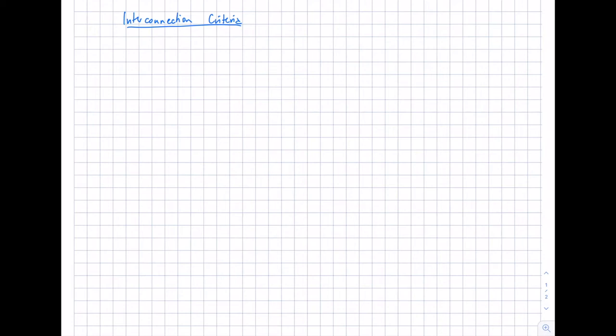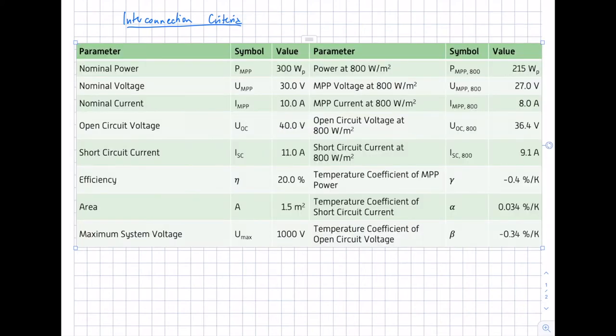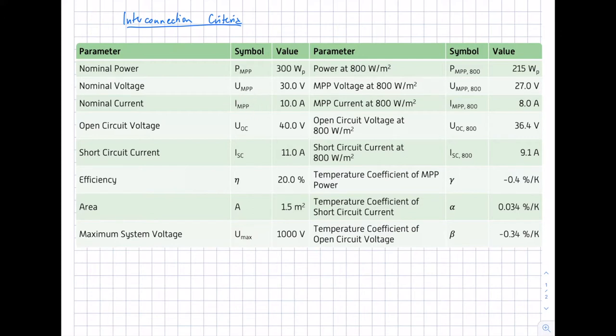First, let's look at a typical datasheet of PV modules. The values you can find on a datasheet are shown here as an example of a monocrystalline PV module. The most important parameters are the nominal power, nominal voltage, and nominal current under standard testing conditions (STC): 1000 watts per square meter irradiance, module temperature of 25°C, and air mass 1.5. Under these conditions, we have an MPP power of 300 watt peak, UMPP of 30 volts, and IMPP of 10 amperes.